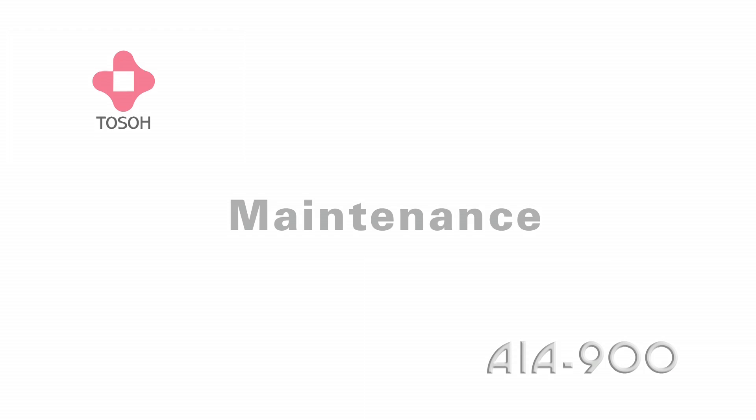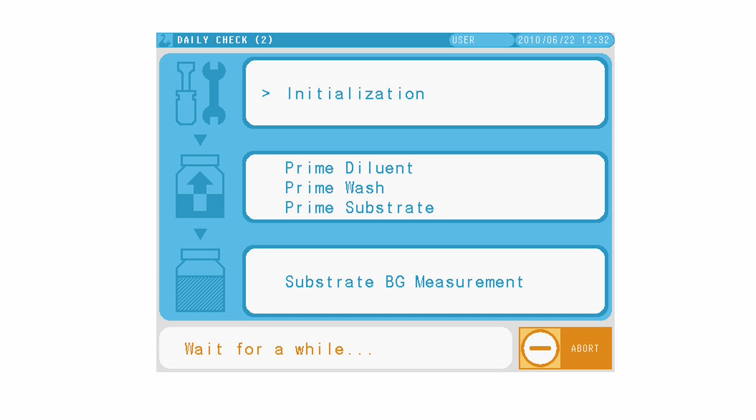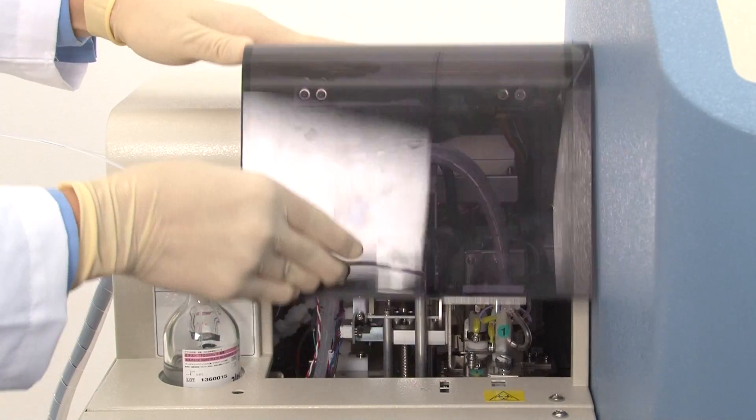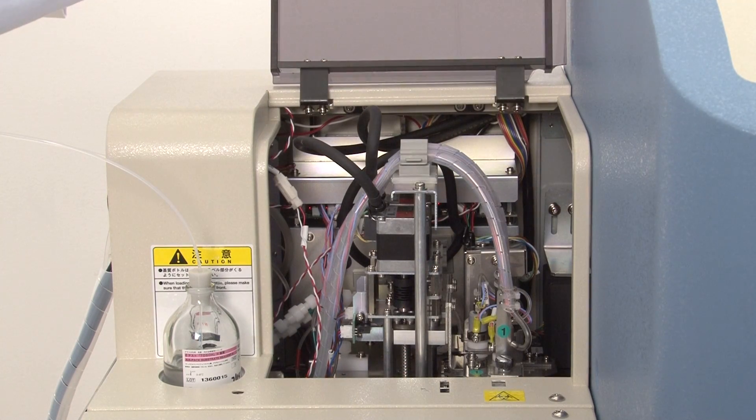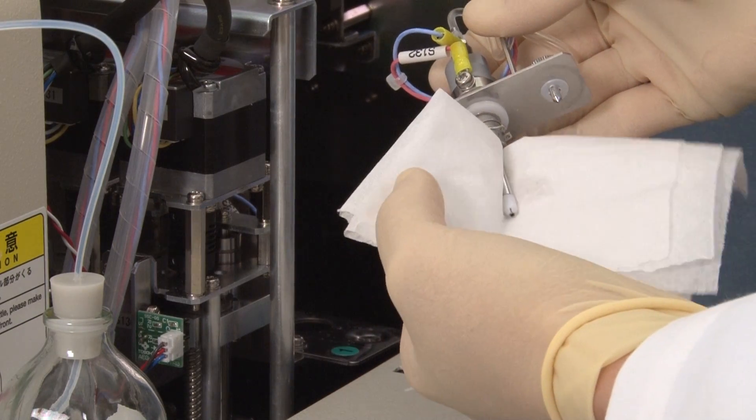Maintenance. Daily maintenance on the AIA 900 is totally automated and requires only five minutes per day at system startup. Weekly maintenance requires only a few minutes of operator time and involves a simple cleaning of the wash probes.